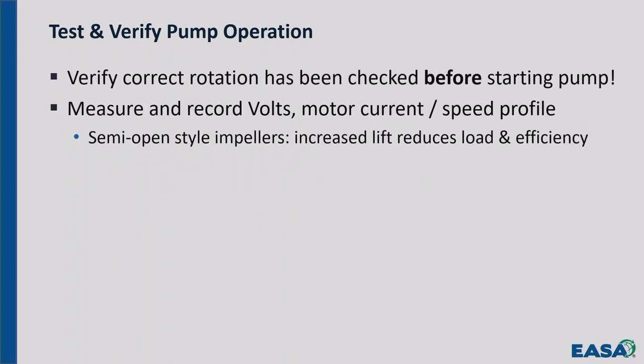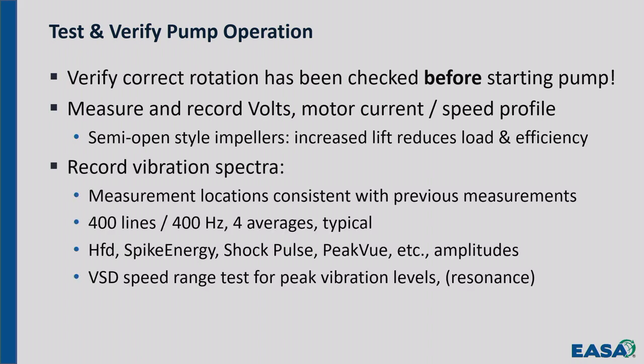All right. Starting the pump. Yep, we did all that. Take vibration spectrum with it running. We recommend 400 lines, 400 hertz, 4 averages as a typical setup. That's probably what your vibration guy does anyway.